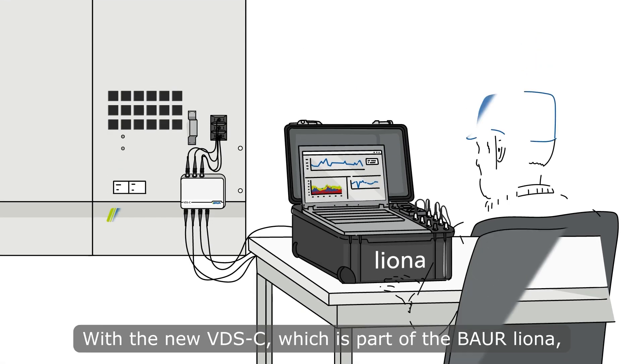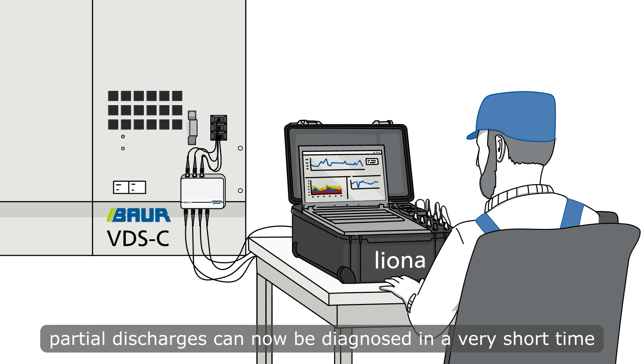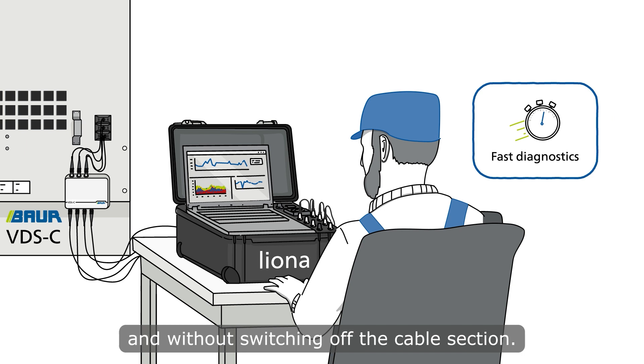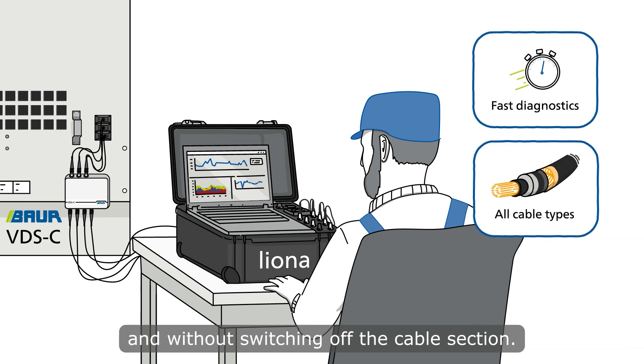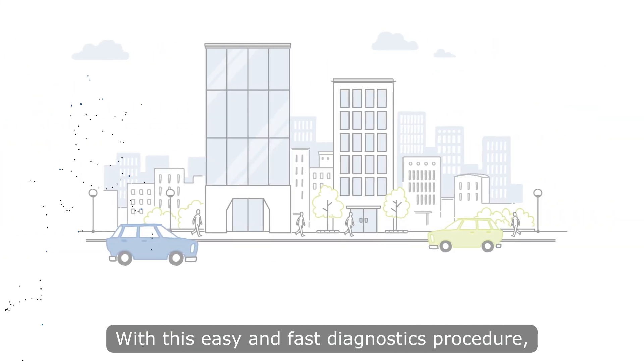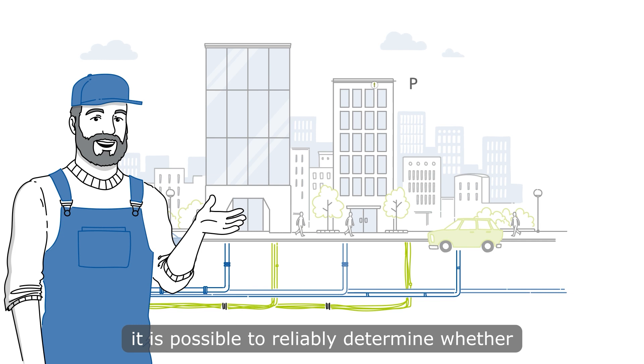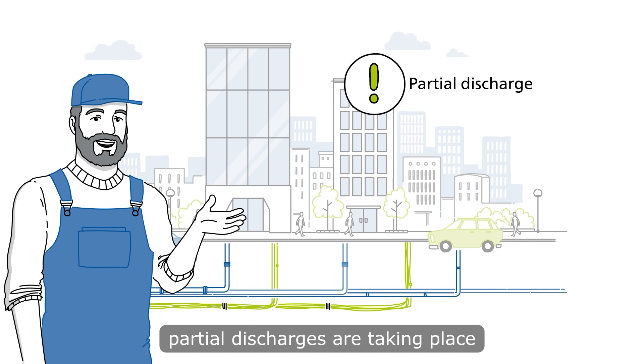With the new VDSC, which is part of the BAUR liona, partial discharges can now be diagnosed in a very short time and without switching off the cable section, no matter which cable types are installed. With this easy and fast diagnostics procedure, it is possible to reliably determine whether partial discharges are taking place anywhere on a medium voltage cable, not only nearby the cable end.